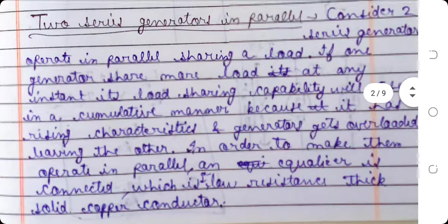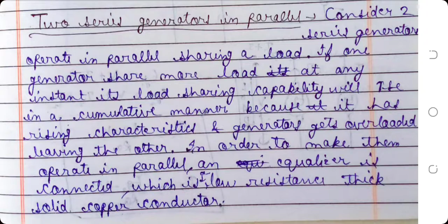Consider two series generators operating in parallel sharing a load. If one generator shares more load at any instant, its load sharing capability will increase in a cumulative manner because it has rising characteristics, and that generator gets overloaded, leaving the other. In order to make them operate in parallel, an equalizer is connected, which is a low resistance thick solid copper conductor.